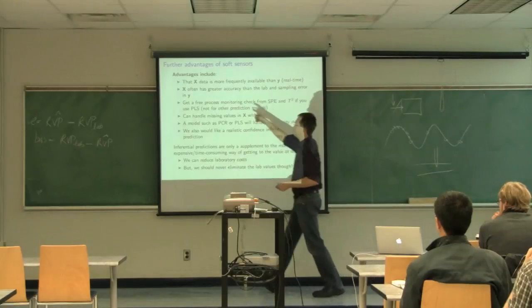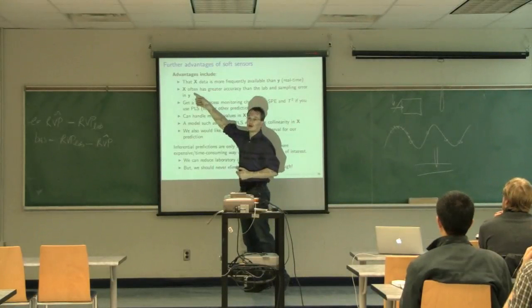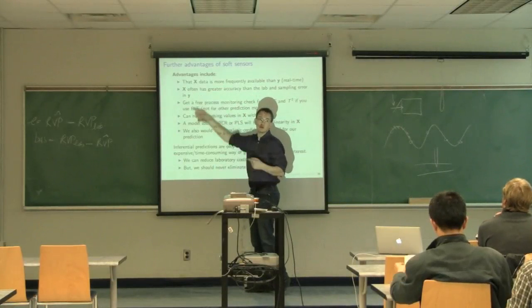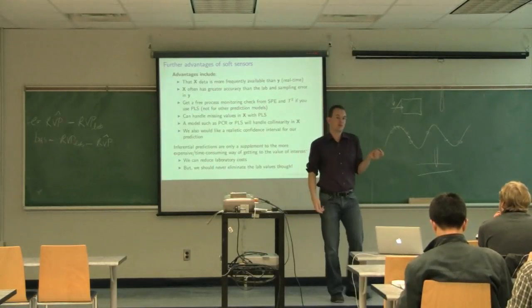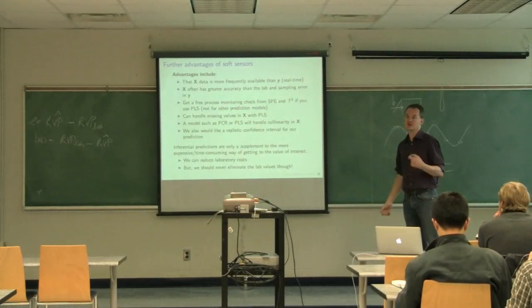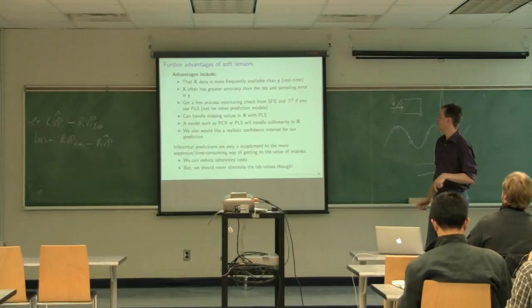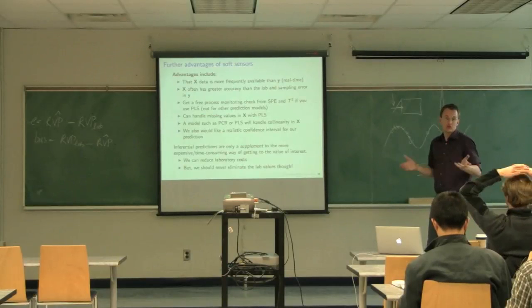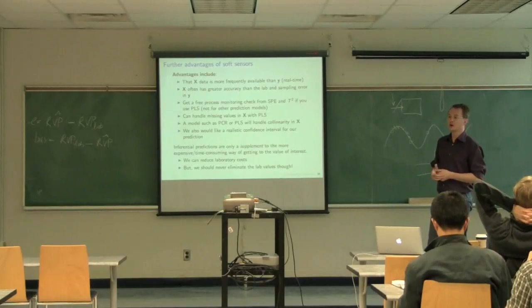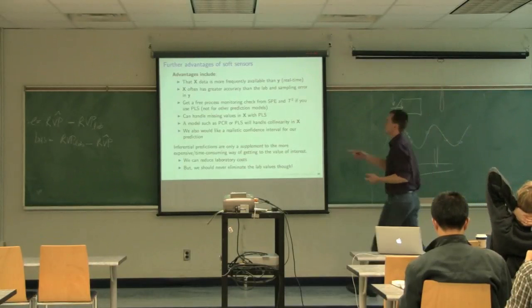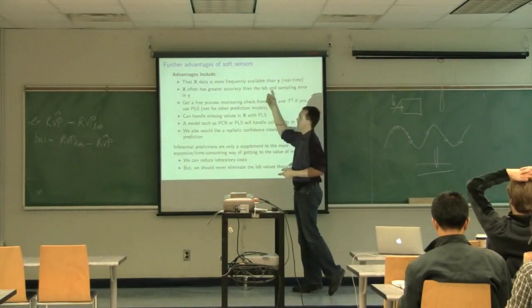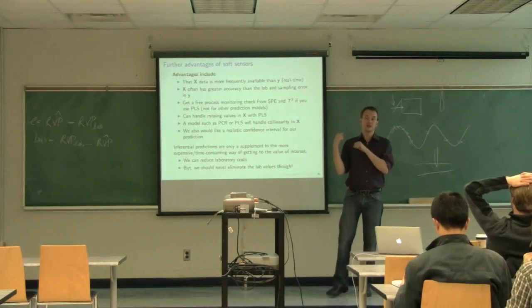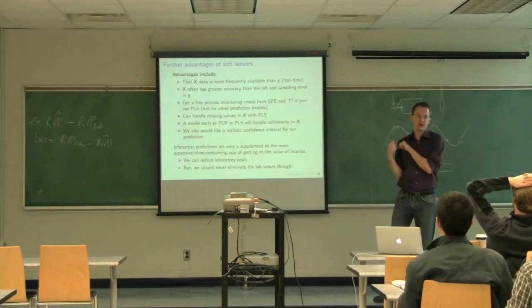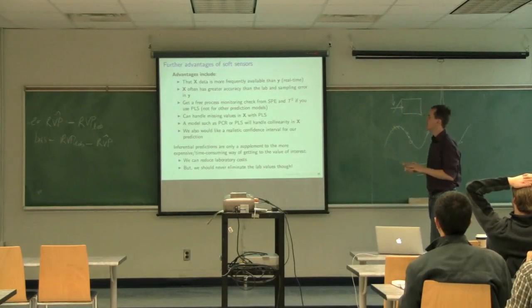But the temperature and pressure variables that go into that predictive model, we can measure temperature within 0.1 degree accuracy, and pressure within a few pascal quite readily with commercial thermocouples and pressure sensors. So we can get our X data at greater accuracy than the lab value. It doesn't mean you're going to predict with less error than the lab value, that would be impossible. But it means at least your inputs going in are going to be fairly accurate.